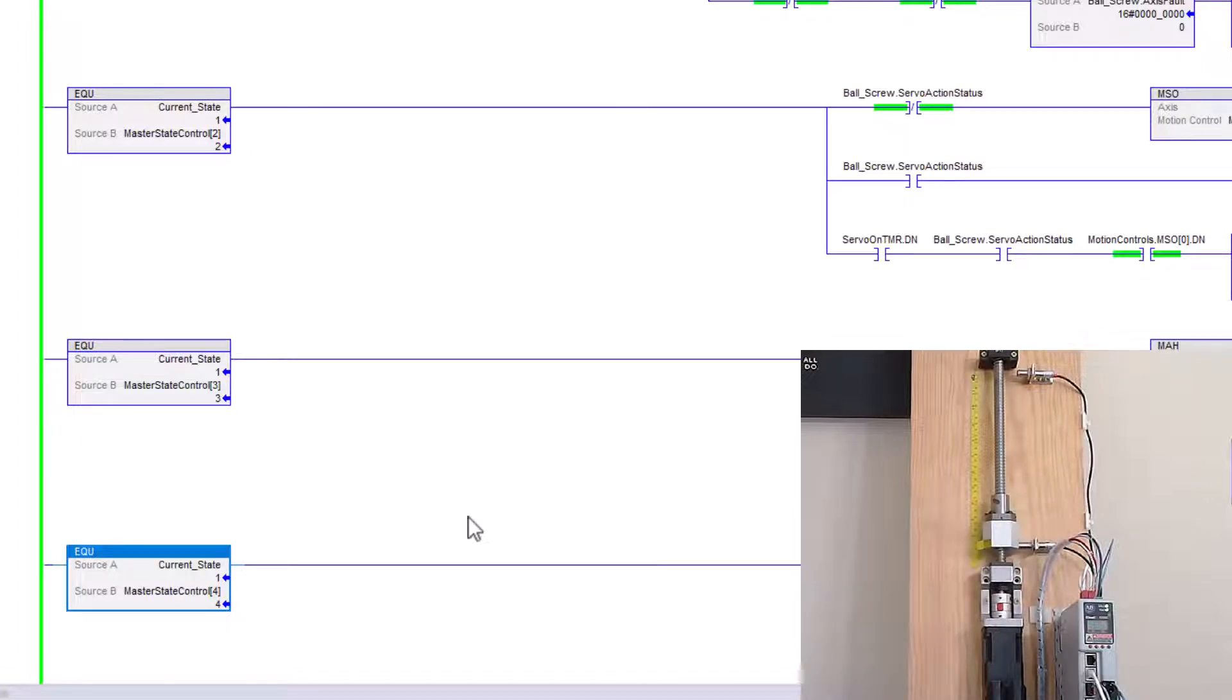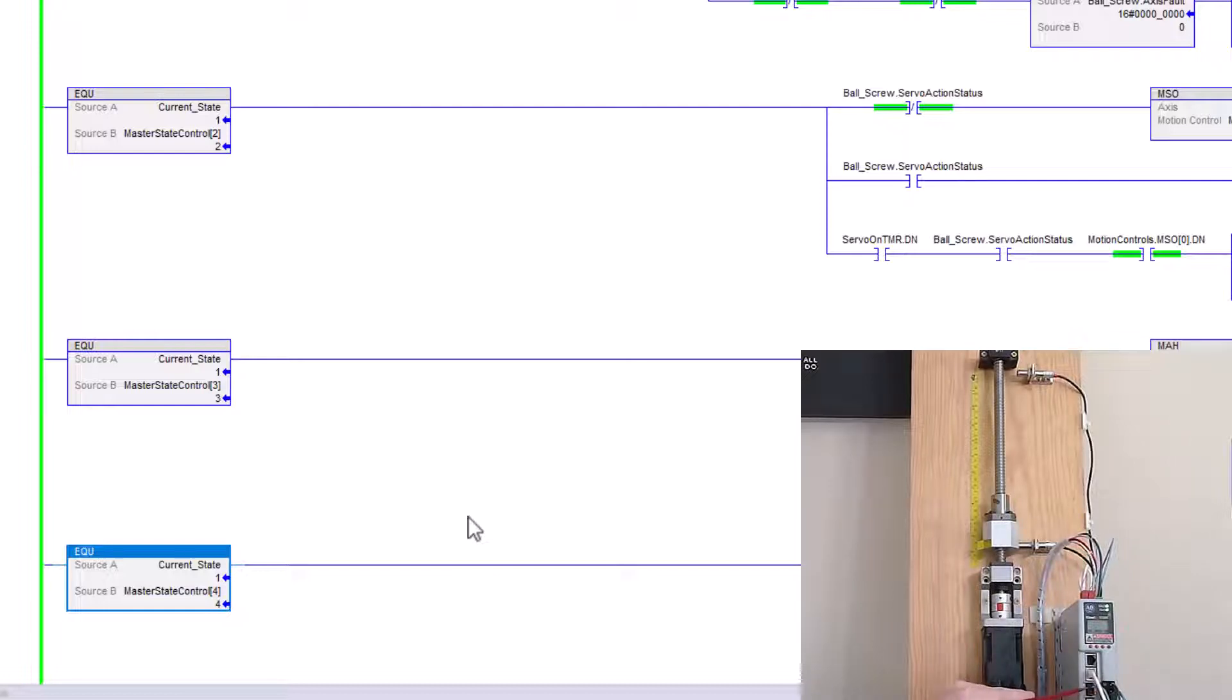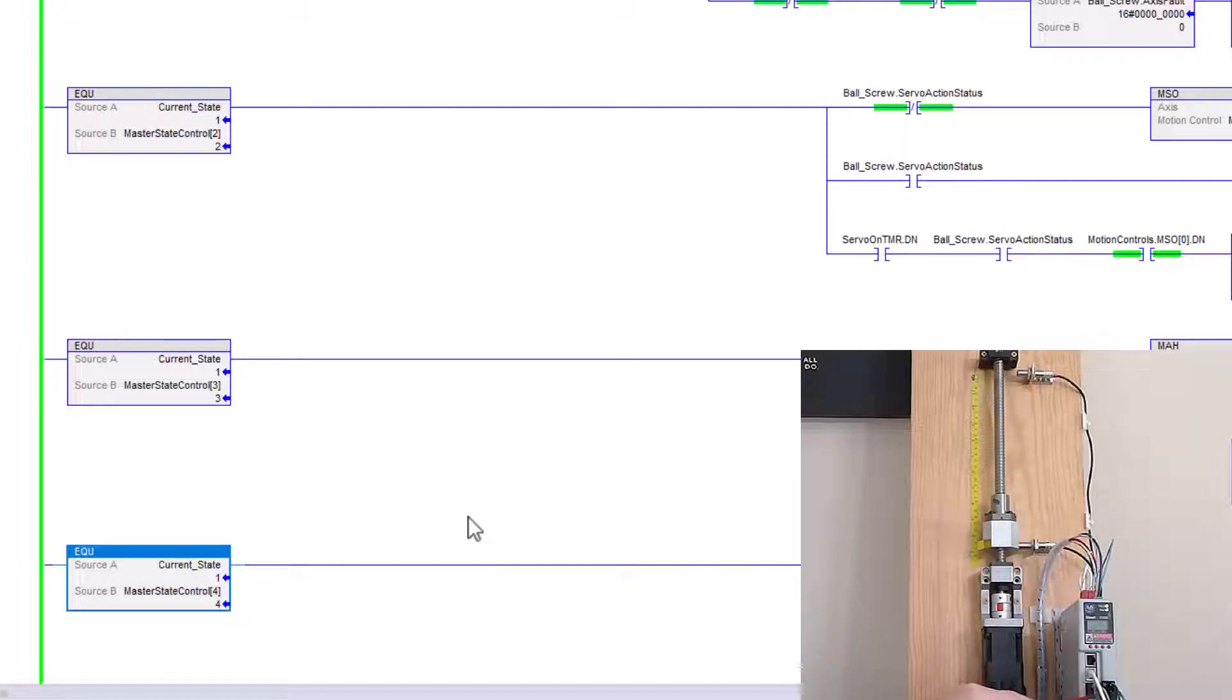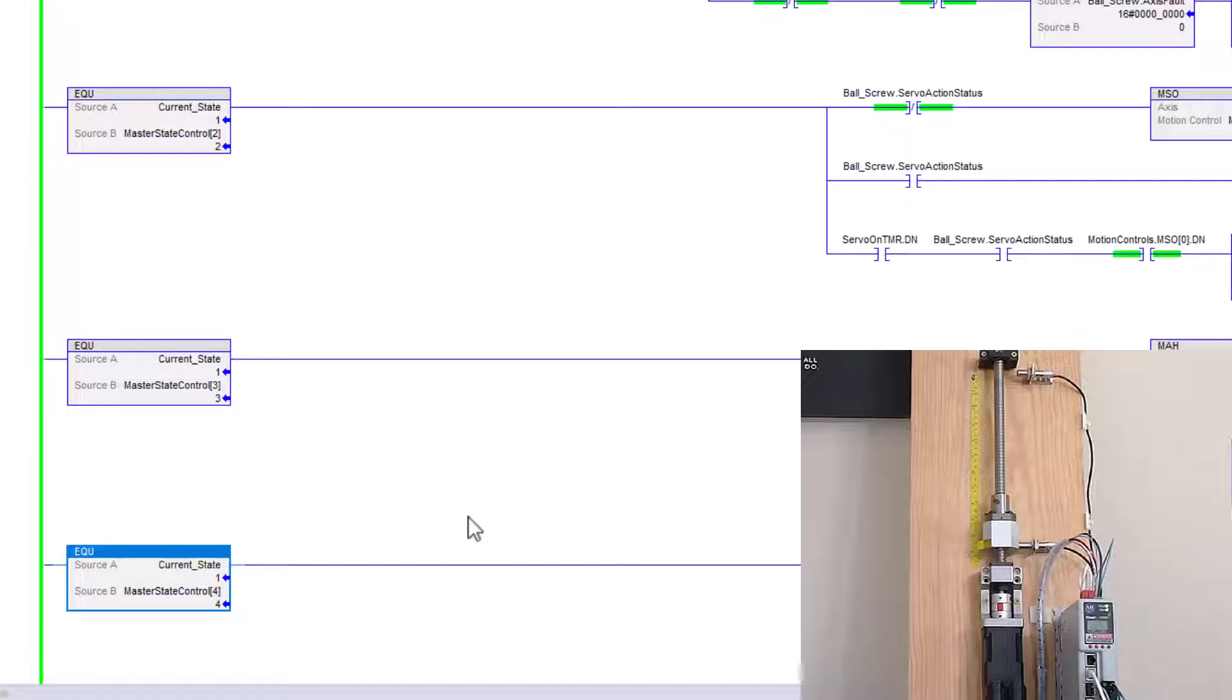Okay. So basically I have my common coming into the common on the Kinetix 5500, and then I have the return on input one. So it's a two wire prox. I don't have to have anything else to that. I just put 24 volts to the actual prox and then get 24 volts back.